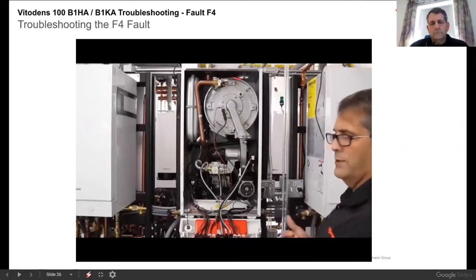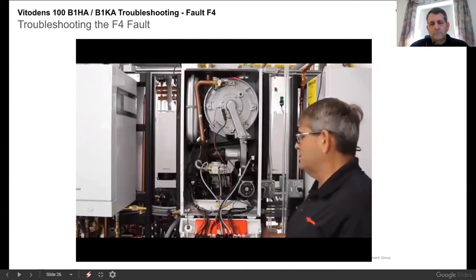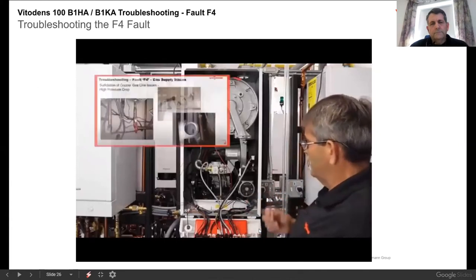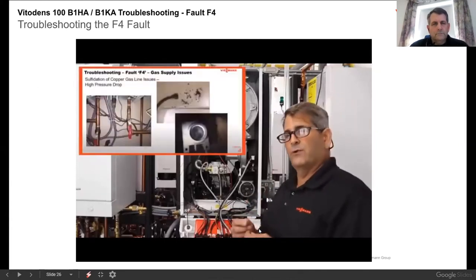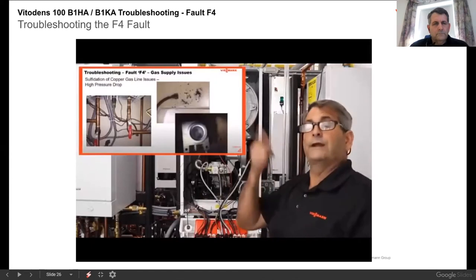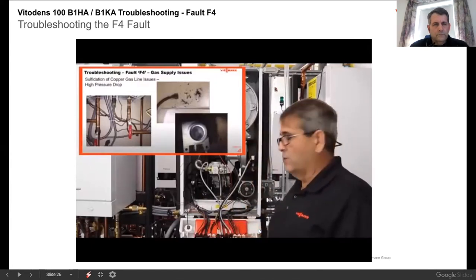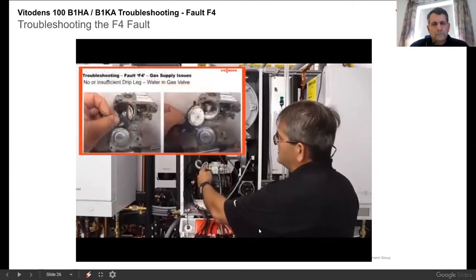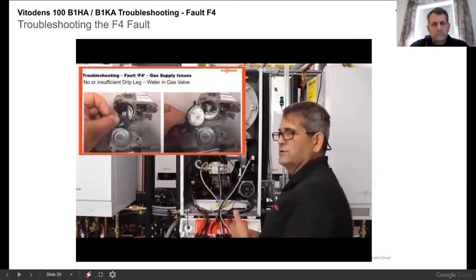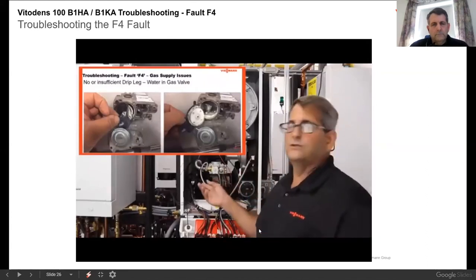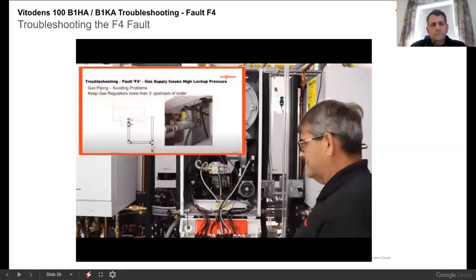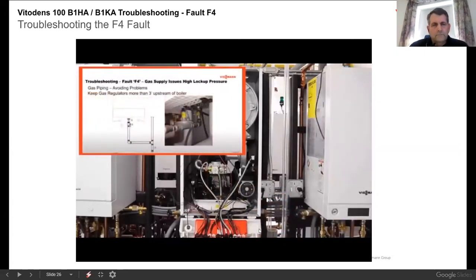Other things you can check, if you're doing propane, are your copper lines. Make sure they're not breaking down from sulfidation, where the propane breaks down the copper tubing, if you're running copper tubing for your gas piping over to the boiler. That will actually start to clog up your gas screen. So during your annual maintenance, it's good to take a look at the inlet gas screen on your boilers, on anybody's boiler really, because of the effects of the gas clogging it.